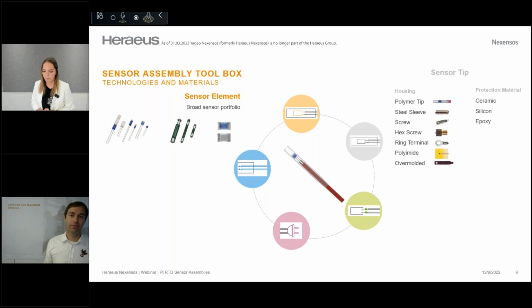Okay, so the next component would be the sensor tip. And you can distinguish the sensor tip into the housing and the protection material. So let's first have a look at the housing. Here is just a selection of what it could look like. We already talked about the first example here. The polymer tip is a semi-rigid, encapsulated housing, and it is very suitable for applications with vibrations, for example. But when you want to work in an application with higher temperatures, then maybe the steel sleeve could be a solution.